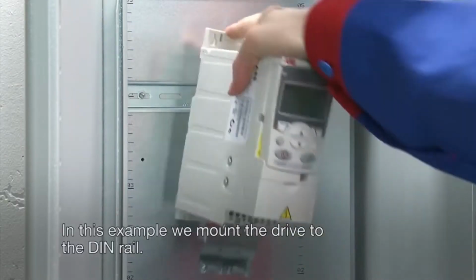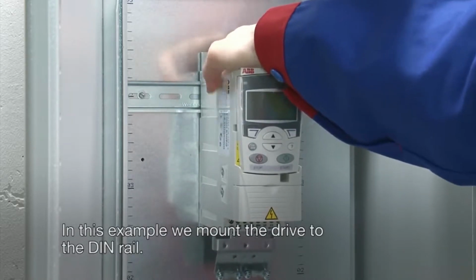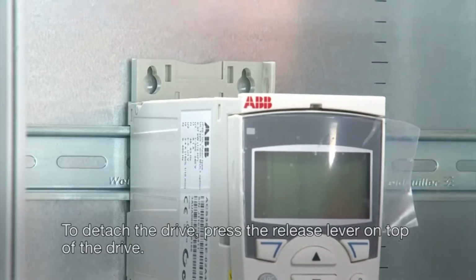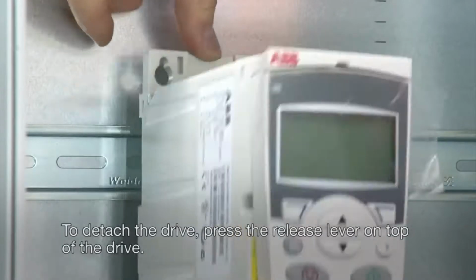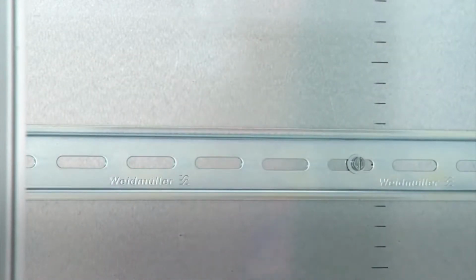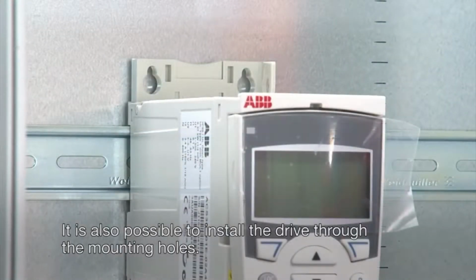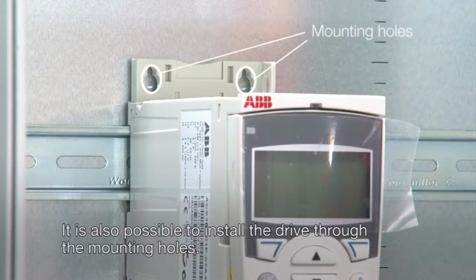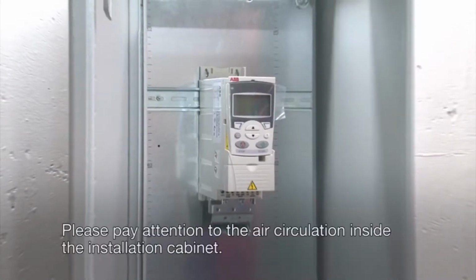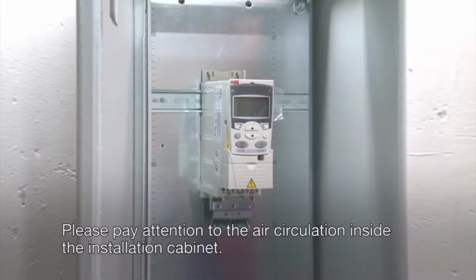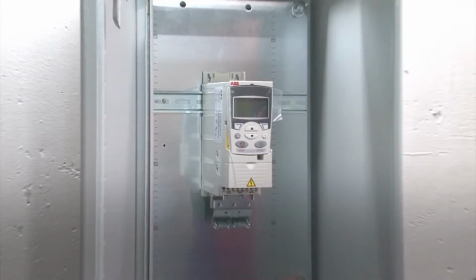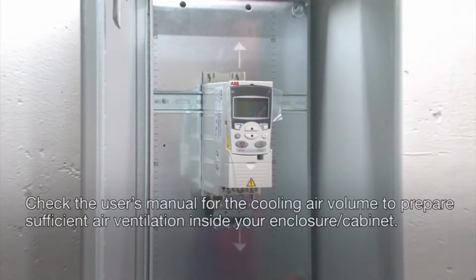In this example, we mount the drive to the DIN rail. To detach the drive, press the release lever on top of the drive. It is also possible to install the drive through the mounting holes. Please pay attention to the air circulation inside the installation cabinet. Check the user's manual for the cooling air volume to prepare sufficient air ventilation inside your enclosure or cabinet.